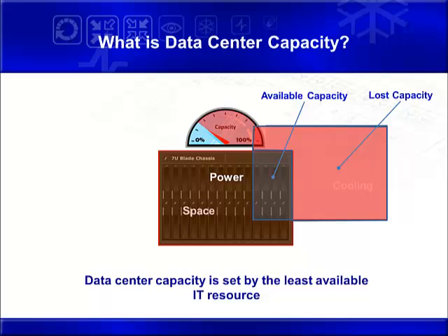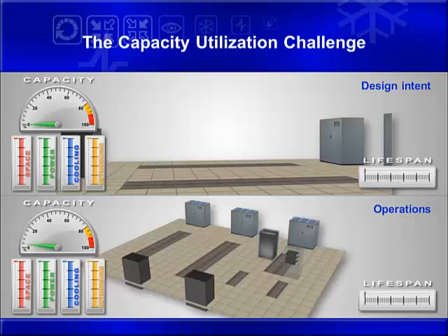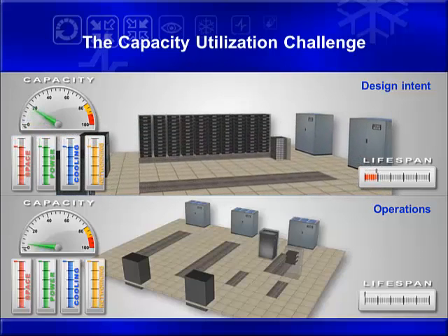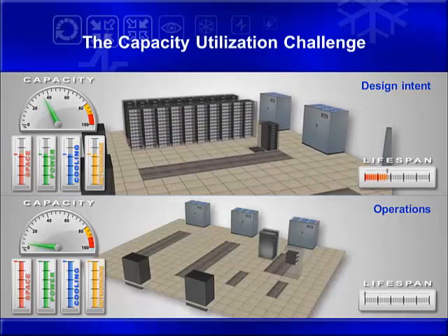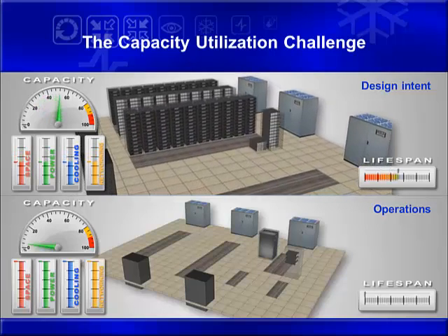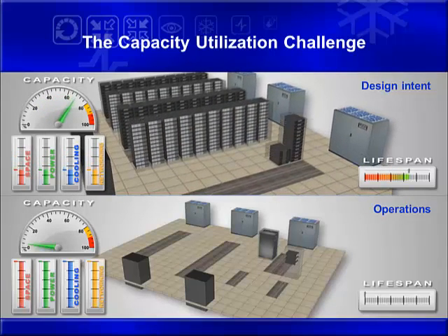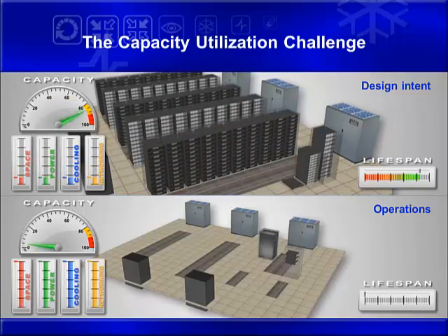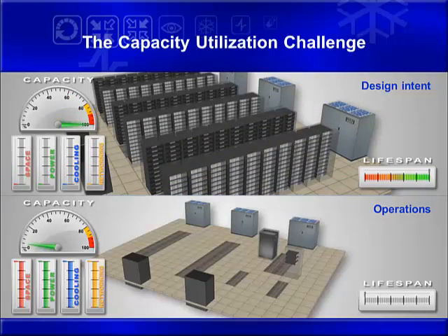So again, data center capacity is the total amount of IT load in kilowatts that the data center can support at desired levels of redundancy. A time-lapse animation of a data center build-out is helpful for visualizing the capacity utilization efficiency challenge. The first animation shows the original build-out plan that was used to design this data center. In design, the facility is designed around an IT configuration plan that is really just a guess at what will actually be built out by operations.